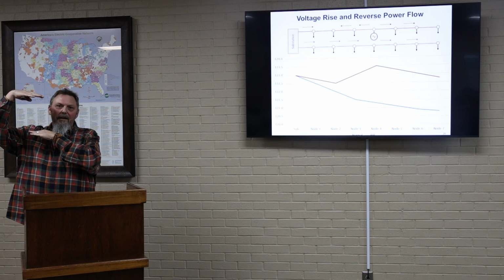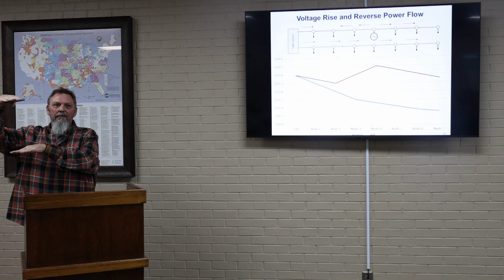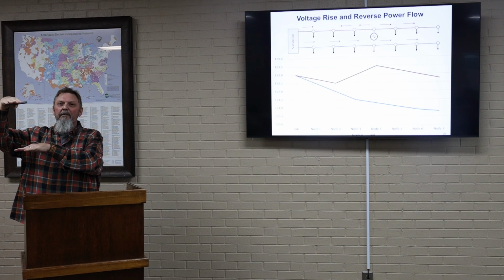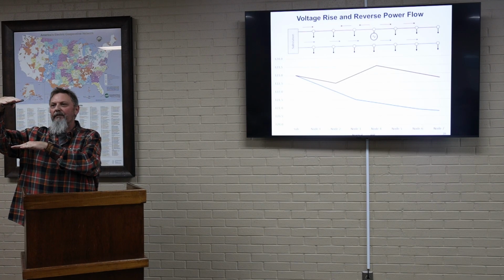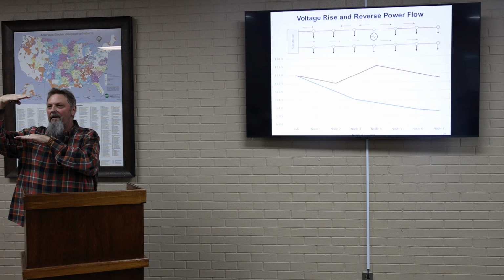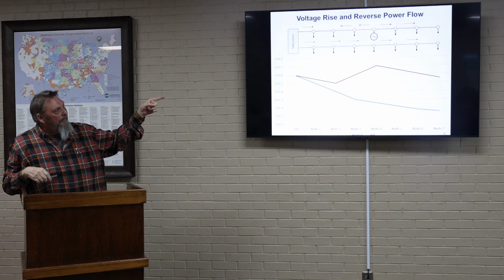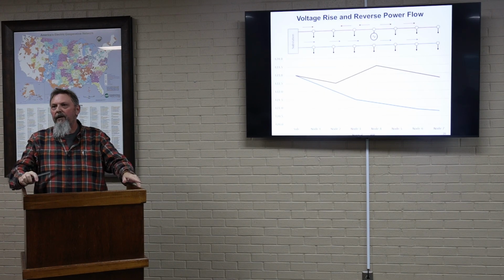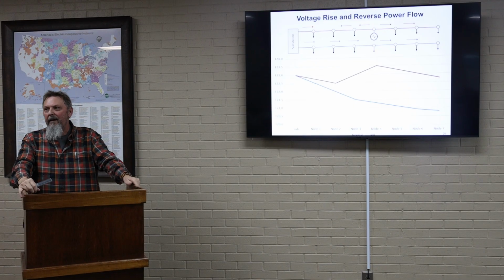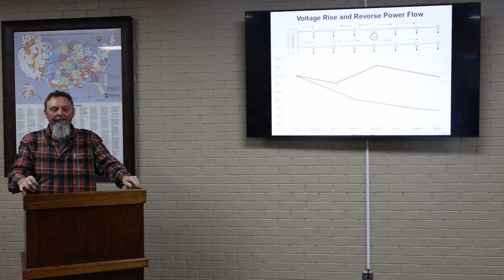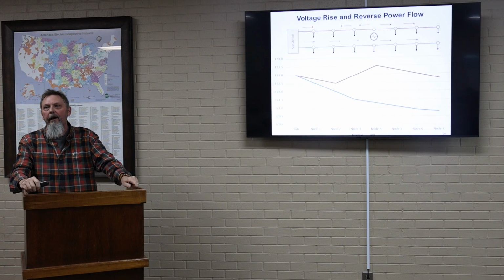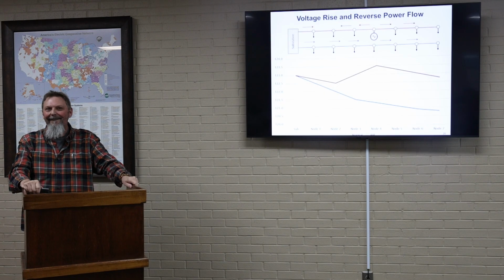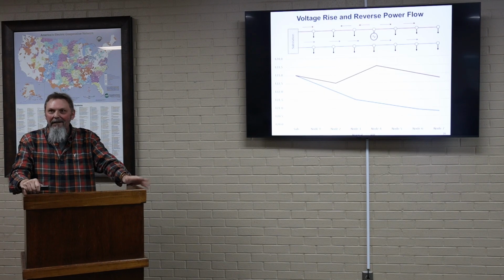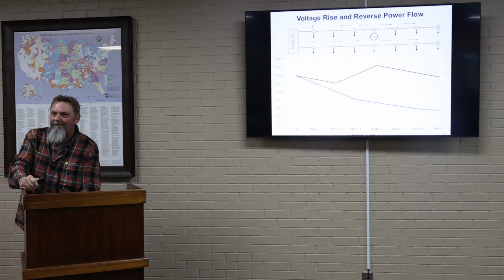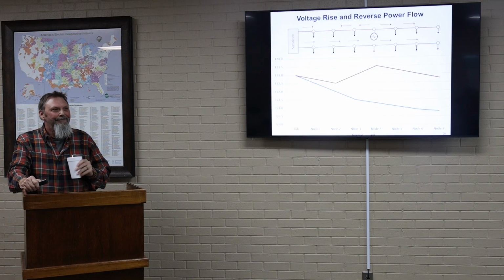So that's the challenge we have, trying to control that voltage and make sure we stay within ANSI standards, because those are the standards we have to follow. We have to be between 118 and 126 volts at your meter, and we have to do that with all these different power flows, and that becomes a real challenge. It's getting harder and harder every day, with 617 of them or something now.